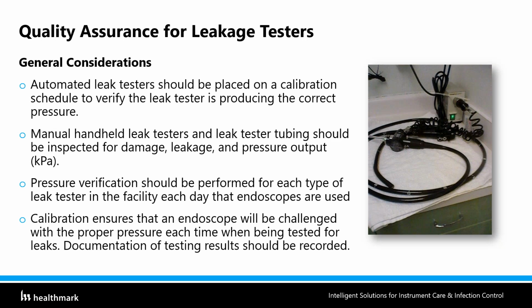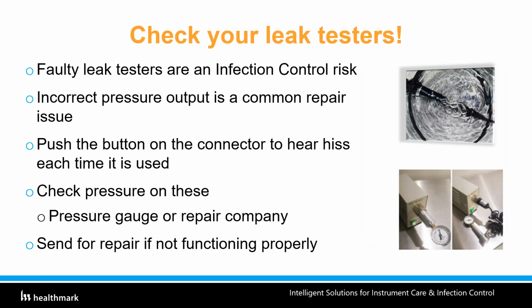Automated leak testers should be placed in calibration mode to do that. One of the things we found when looking at the IFU for these leak testers is a button, and it said that you push the button, and if you hear hissing, then you're in good shape. Looking at that, a faulty leak tester is really an infection control issue. As you saw, for example, in that scope that was sent for repair, they found all that gunk inside it.